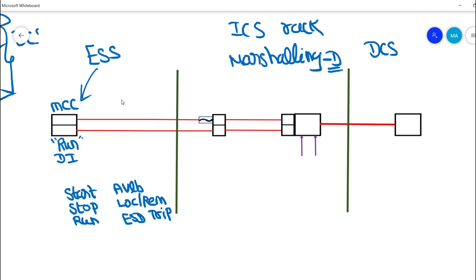The run feedback signal is looped to the marshalling panel where we have an interface TB — called a knife-edge TB — with a fuse rating. For example, we use 100 milliamp. Depending on the loop voltage of MCC and DCS, this fuse rating is chosen. That would be a glass fuse, and 100 milliamp is taken here as an example.